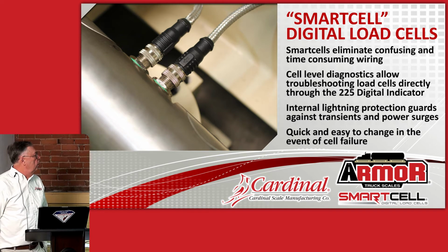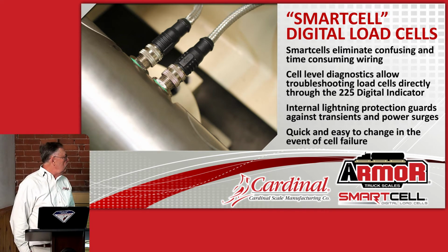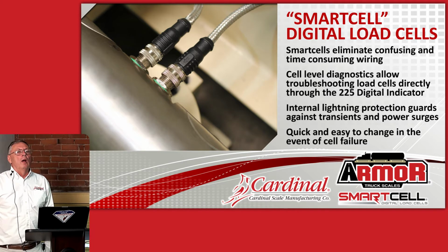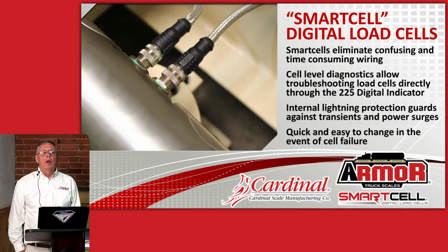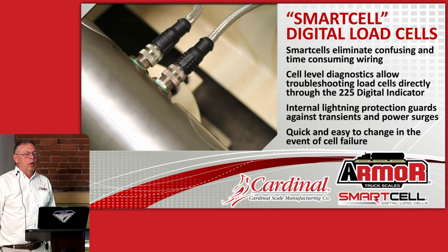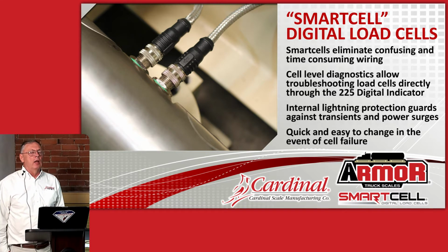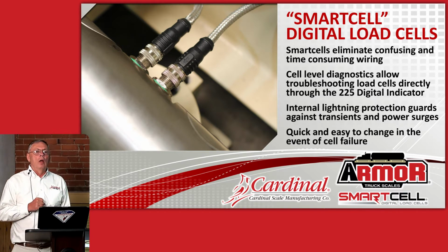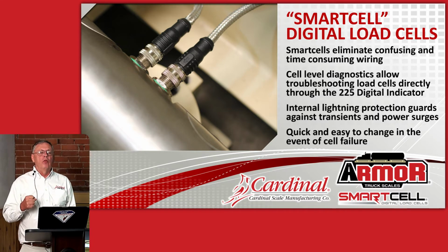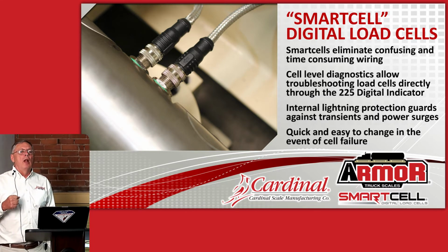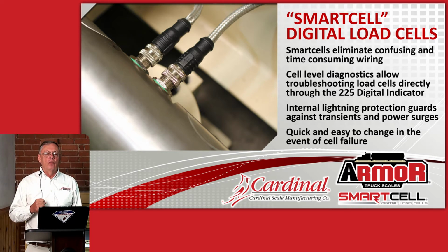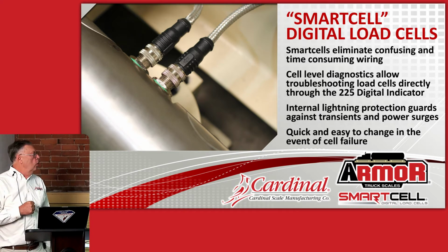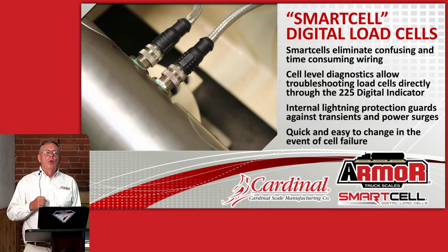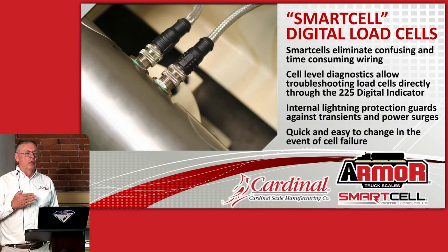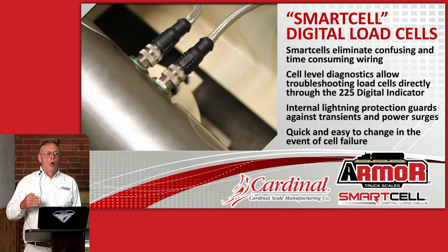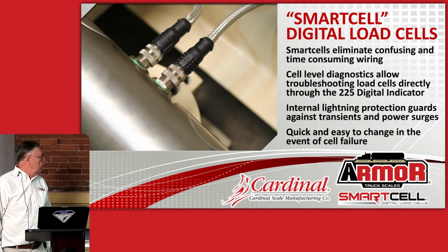This is our new double-ended beam digital SmartCell. Our new digital SmartCells are calibrated internally so that they are linear to their full capacity. Unlike an analog load cell, where the output of the cell is set at 2 millivolts per volt, and then you have to deal with whatever error curve is there, internally, our new digital load cells are calibrated by dropping a test weight on them every 10,000 pounds, all the way to capacity. So it should be very, very linear.